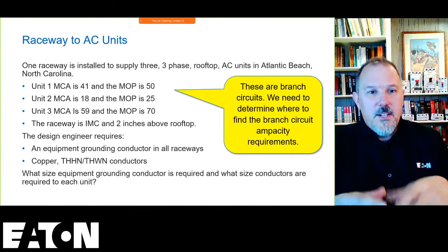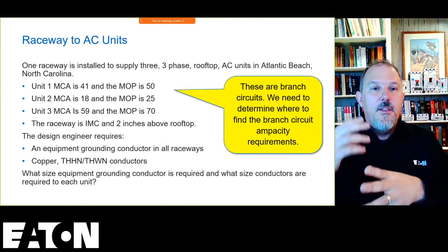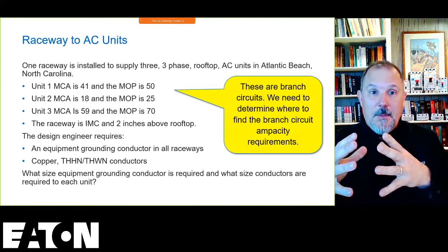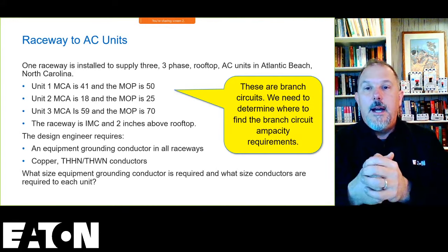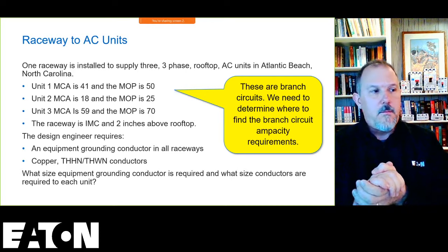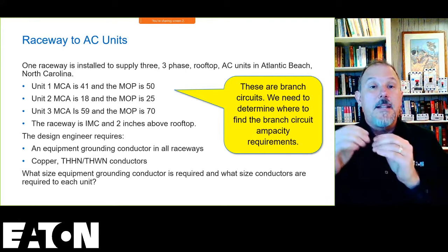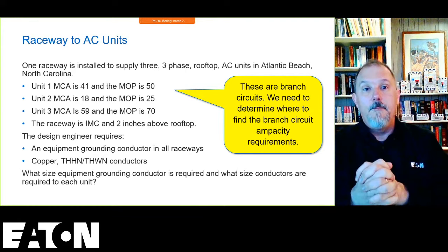All right, so one raceway is installed to supply three-phase rooftop AC units in Atlantic Beach. So what does that tell me? I know that I have three-phase, and I'm going to AC units. So I know how many conductors I have per unit, so I can calculate how many conductors I have in that raceway.